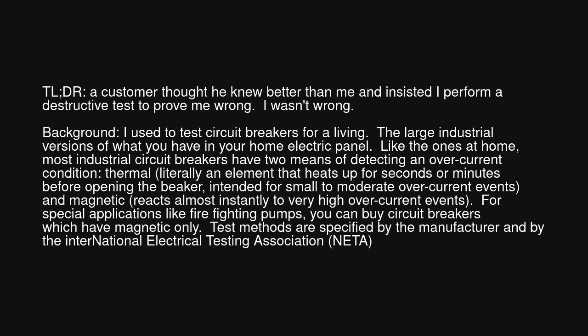Like the ones at home. Most industrial circuit breakers have two means of detecting an overcurrent condition. Thermal. Literally an element that heats up for seconds or minutes before opening the breaker. Intended for small to moderate overcurrent events. And magnetic. Reacts almost instantly to very high overcurrent events. For special applications like firefighting pumps. You can buy circuit breakers which have magnetic only. Test methods are specified by the manufacturer and by the International Electrical Testing Association.